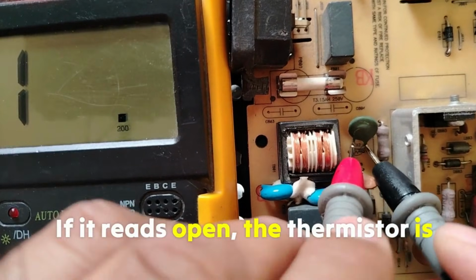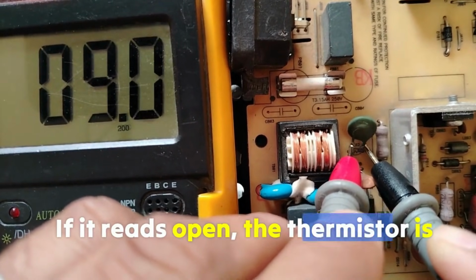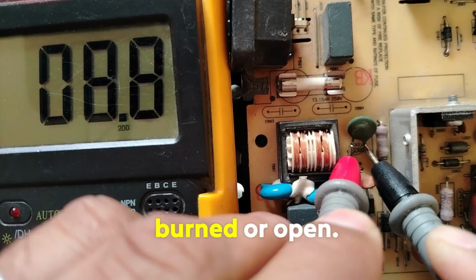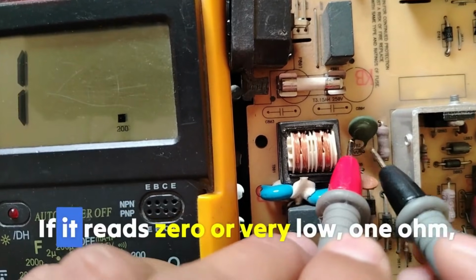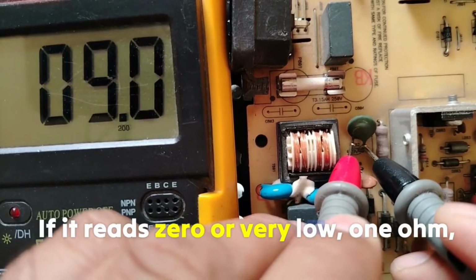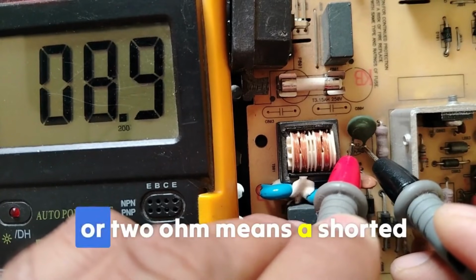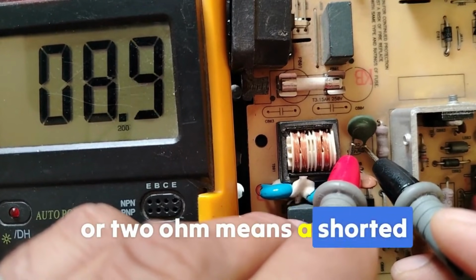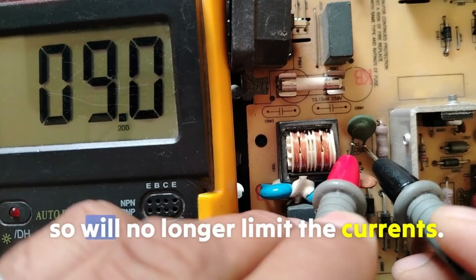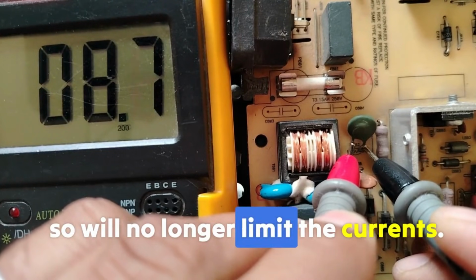If it reads open, the thermistor is burned or open. If it reads 0 or very low, 1 ohm for example, or 2 ohm, it means a shorted thermistor, so it will no longer limit the current.